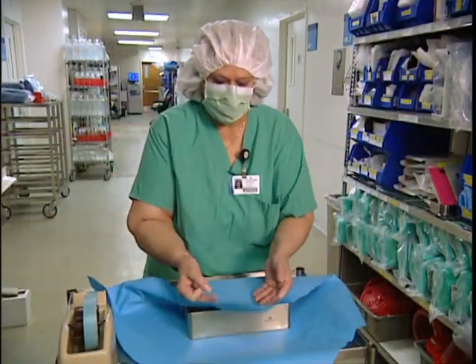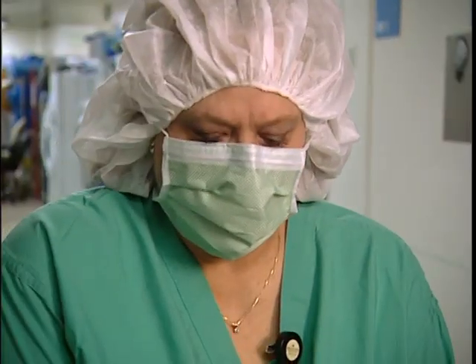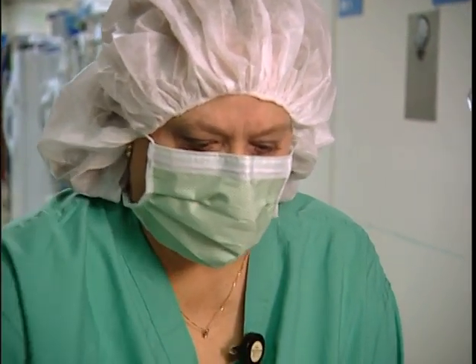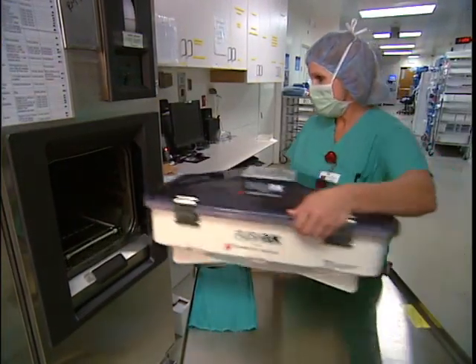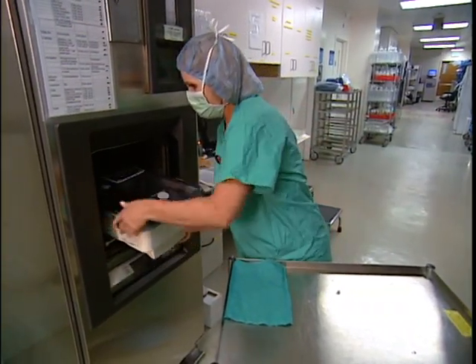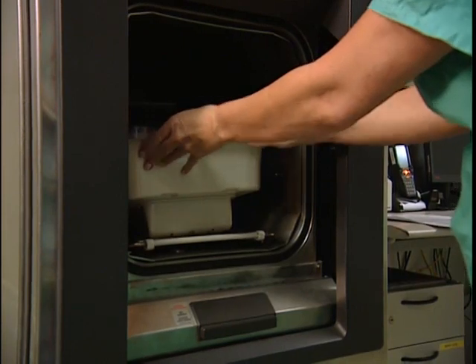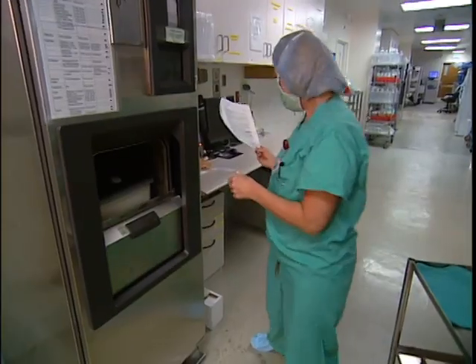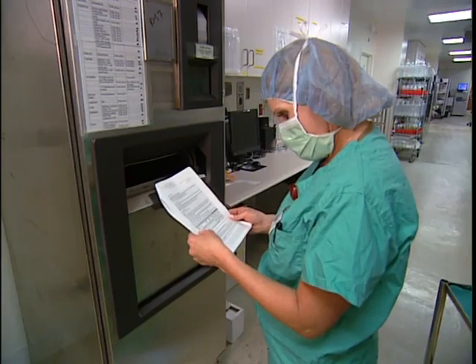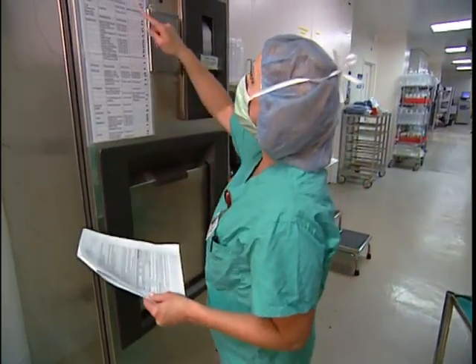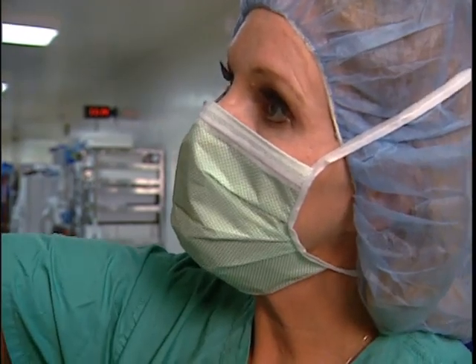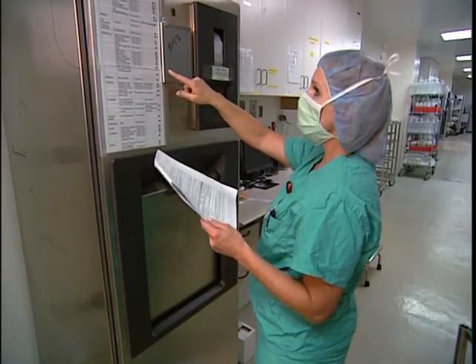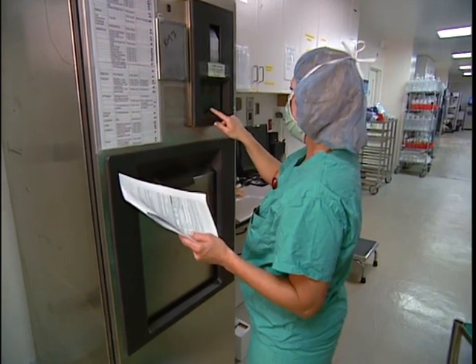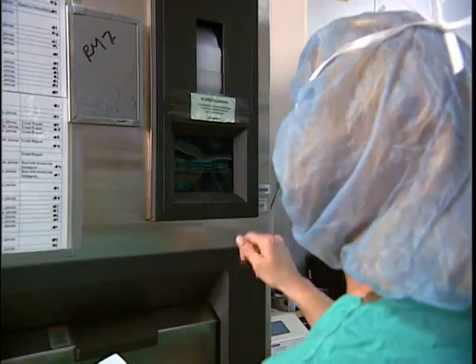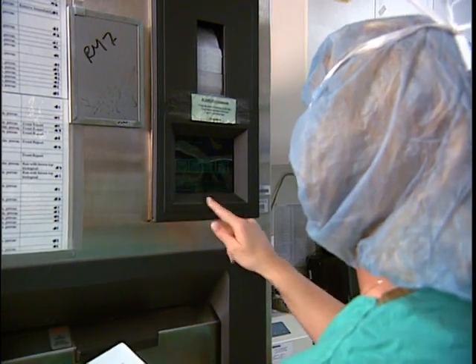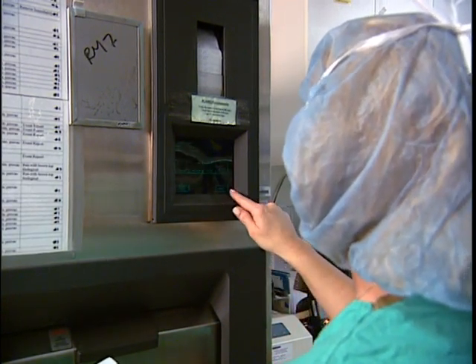Regardless of the type, if you are called upon to utilize an immediate use steam sterilizer, then you must remember the following rules. It is vital that immediate use steam sterilization be utilized in accordance with professional guidelines, your facility's policies and procedures, as well as in strict compliance with validated written instructions provided by device manufacturers, sterilization equipment manufacturers, and container or textile manufacturers. This is especially critical for short sterilization cycles, as it takes time for steam to penetrate a sterilizer load and achieve an acceptable sterility assurance level.